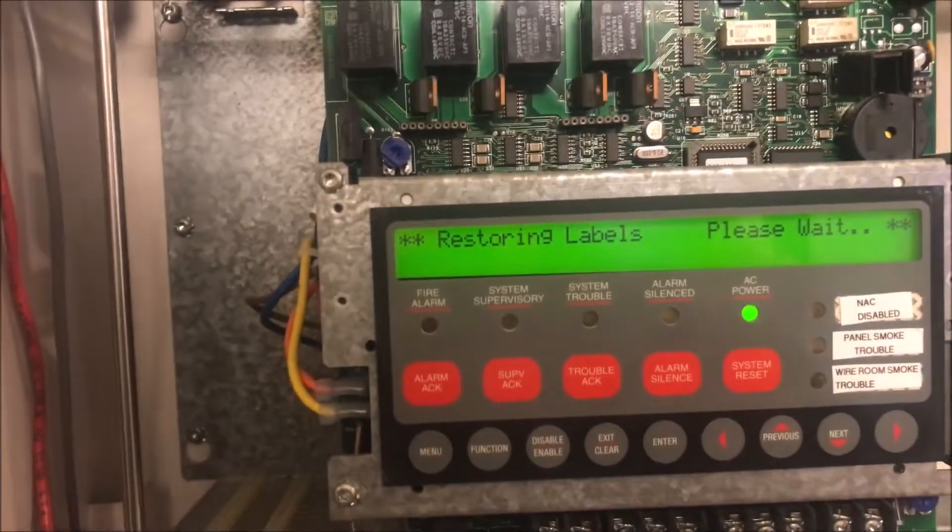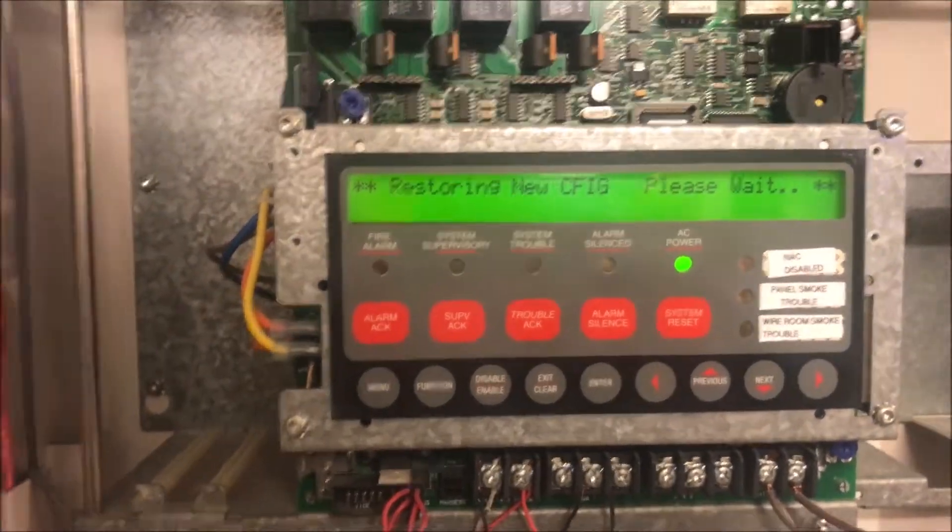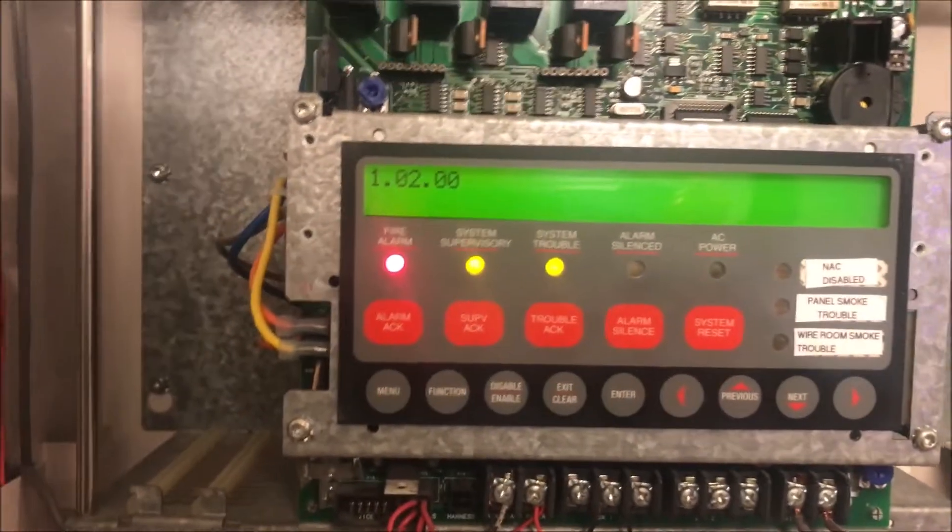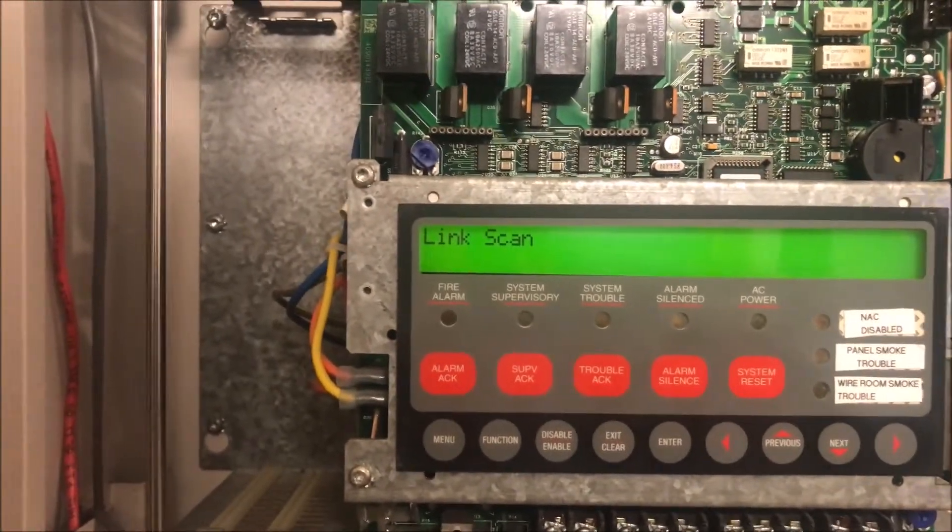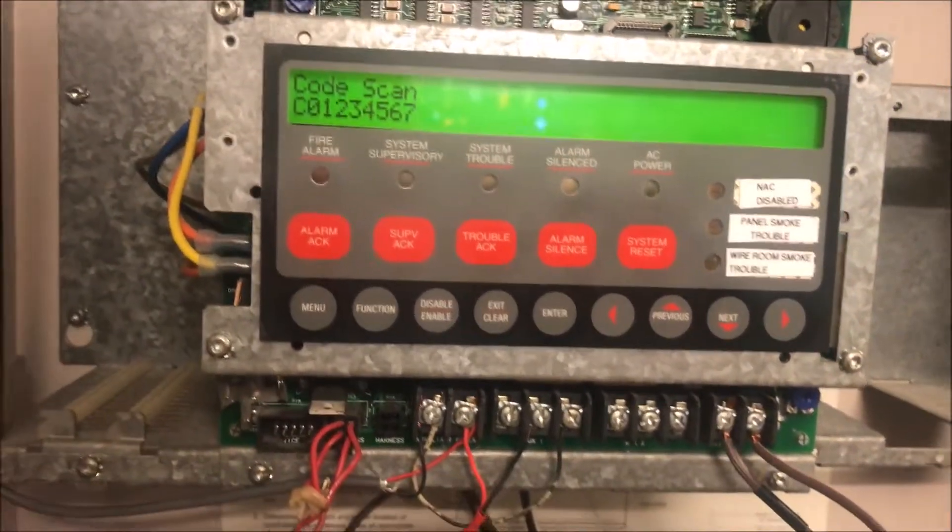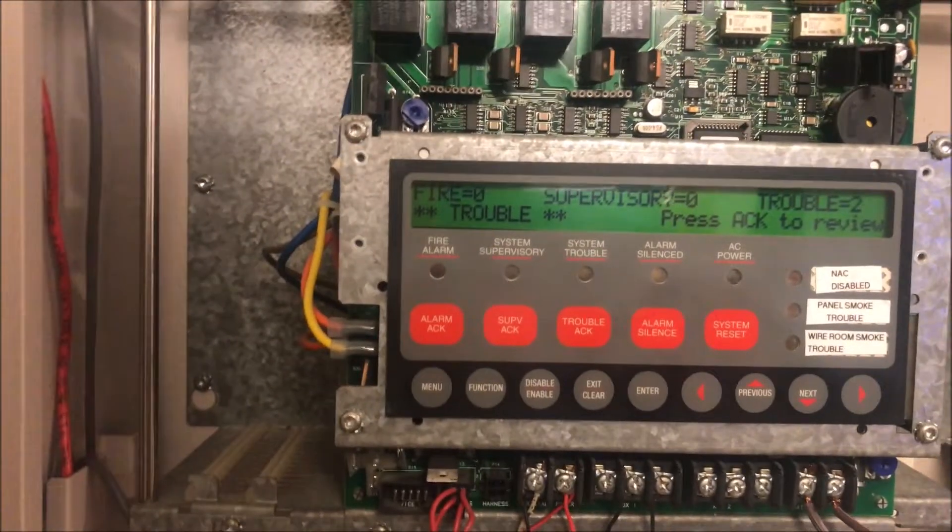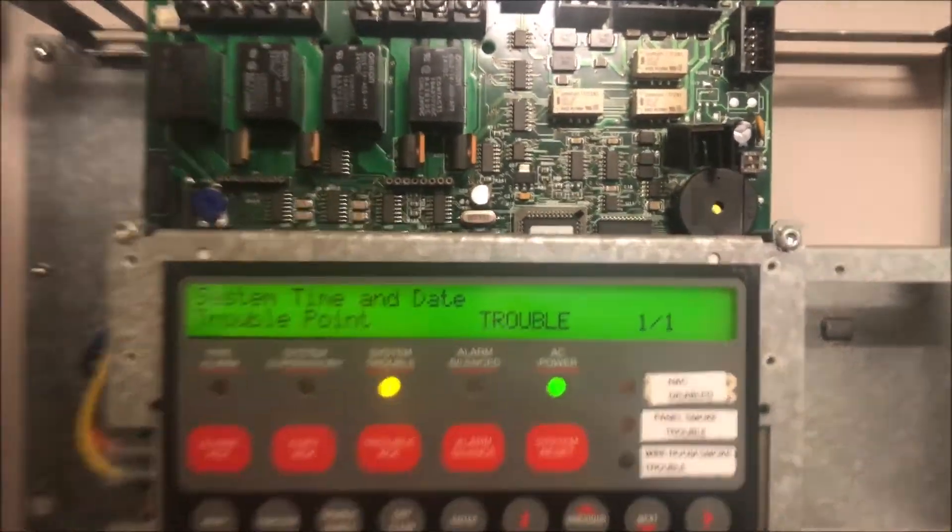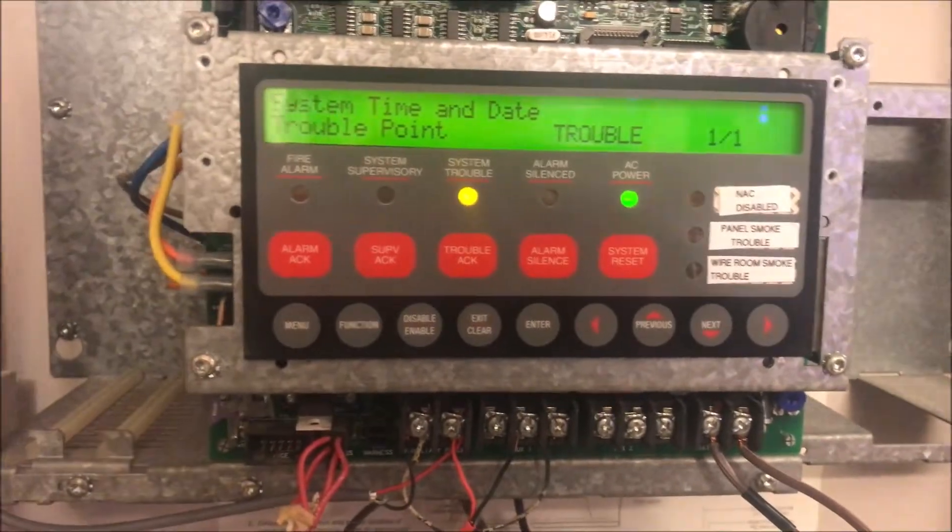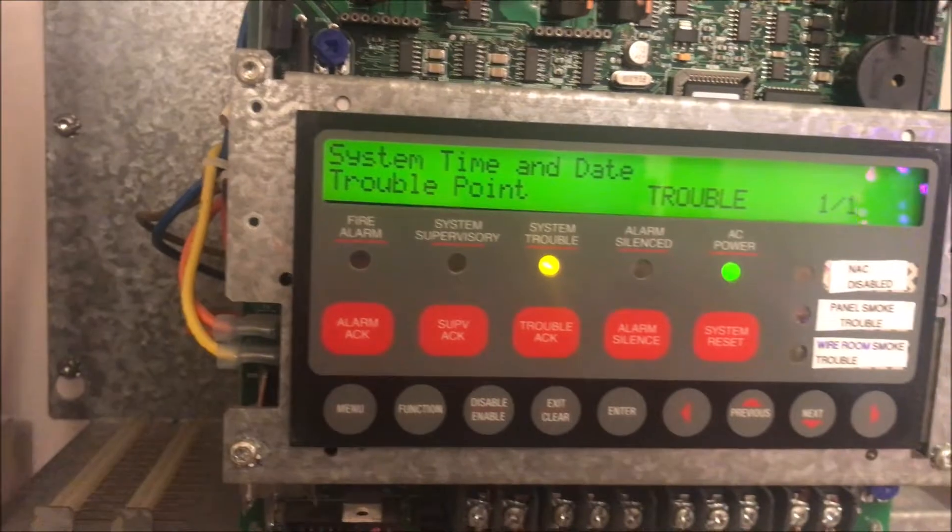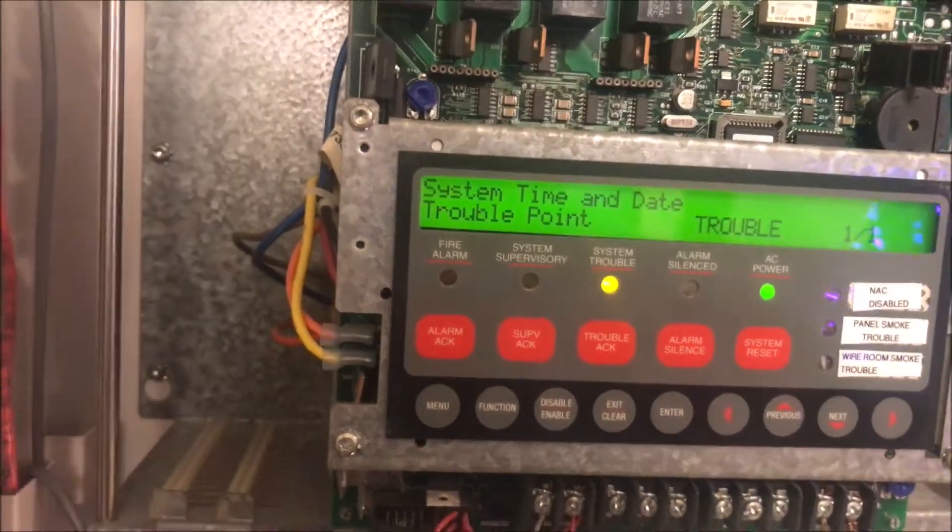Now that we have the new point in, it is going to clear the extra device trouble. You still hear the annunciator blaring in the back - it will restart just like the panel does. Once it goes to startup, the annunciator will clear. There we go. Now our troubles are a cold start and system time and date. A cold start clears automatically and we have no other troubles.